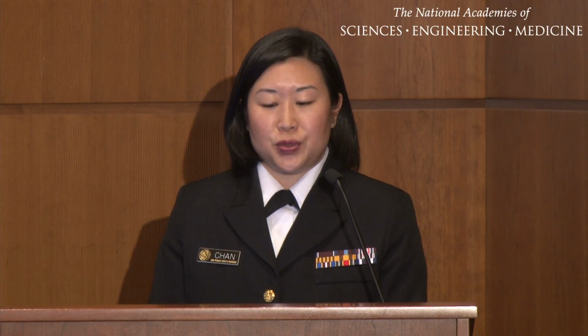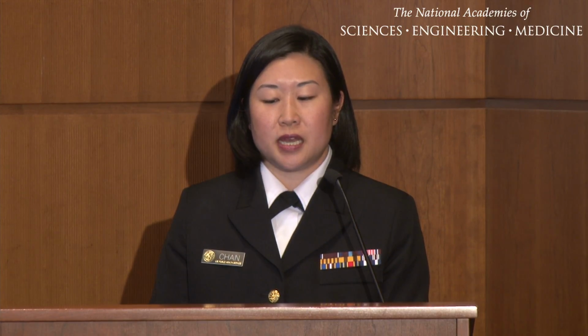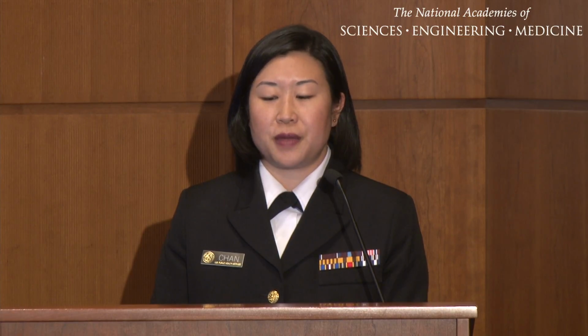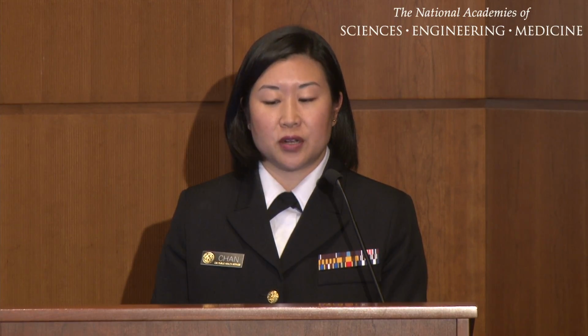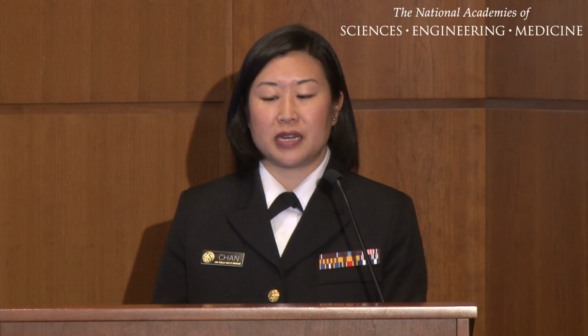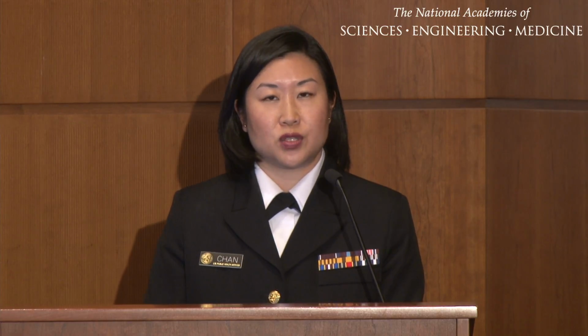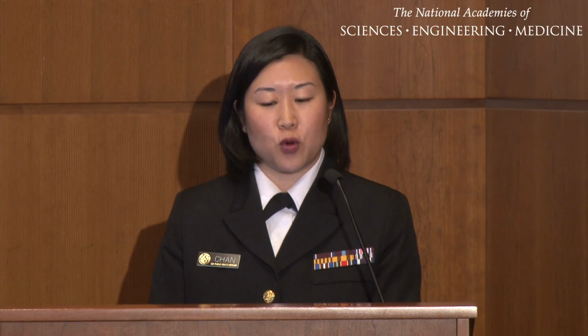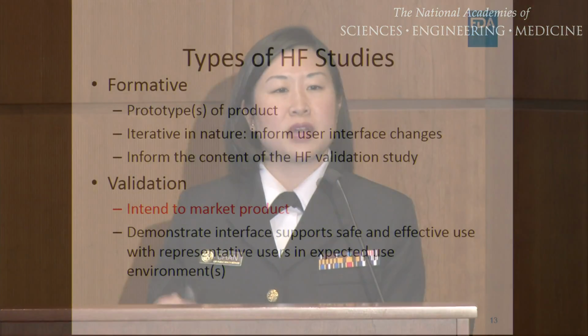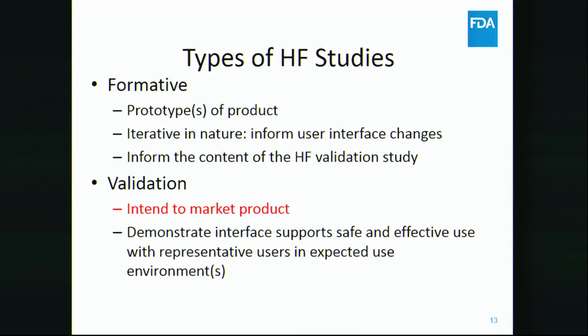So moving on to another guidance. This was a draft guidance that was recently published in February. It's human factor studies and related clinical study considerations in combination product design and development. And, when we talk about human factor studies, there's sort of two main buckets. We talk about formative studies, which is the design process that is iterative in nature. You're taking perhaps you're rapidly prototyping, and you may not have a final finished form, but you're using different models and working through them to understand, how do I continue to refine the labels and labeling?